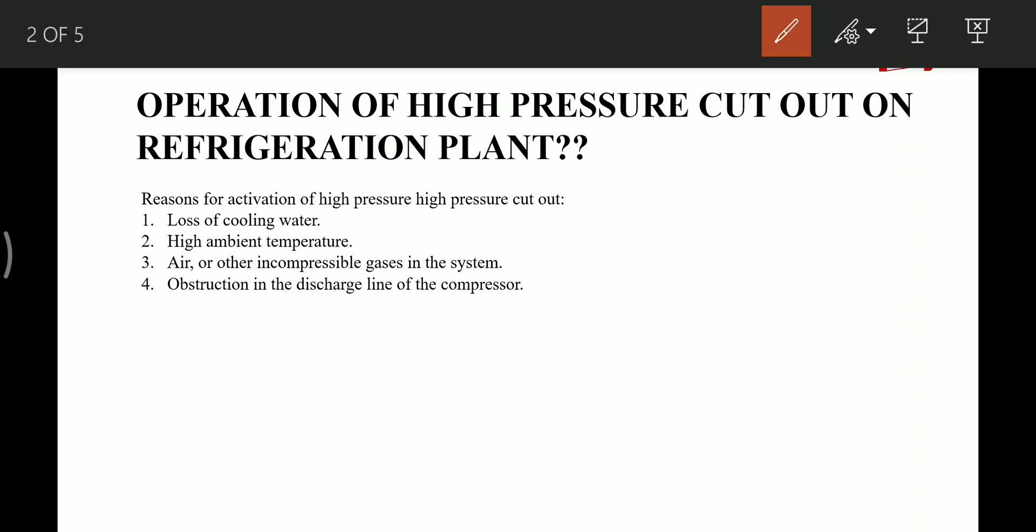The first reason is the loss of cooling water. This can take place in case of pump failure, or when the pump is operating but the pressure is not sufficient as required by the system.